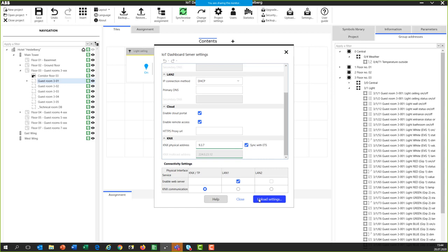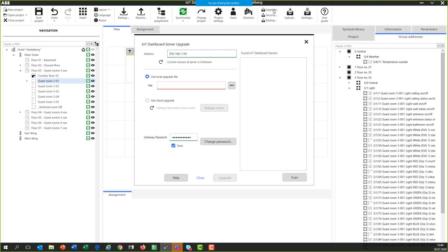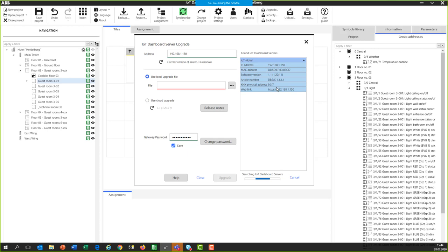Here you can see the communication via twisted pair — one of the first steps. If you're unsure about having the latest software version, click the 'Upgrade' button and 'Scan'. You get a list of all IoT Dashboard Servers in your local IP network. The current software version is 1.2011, which is the latest. If you have an older version, you can update via the cloud or by downloading the update file from abb.com/knx, storing it locally, selecting the folder, and starting the update manually.